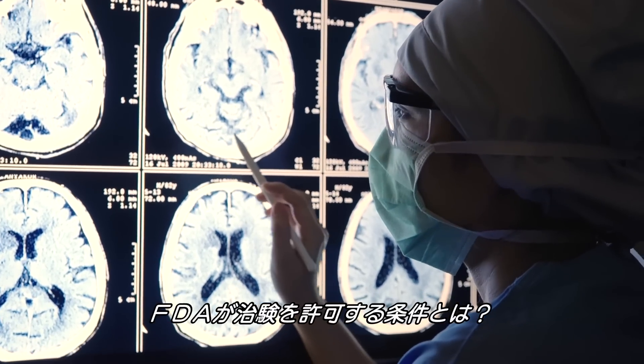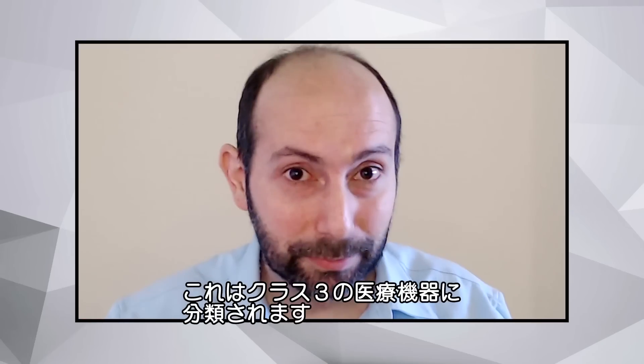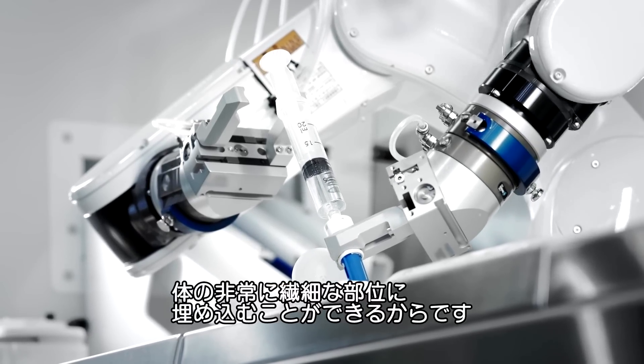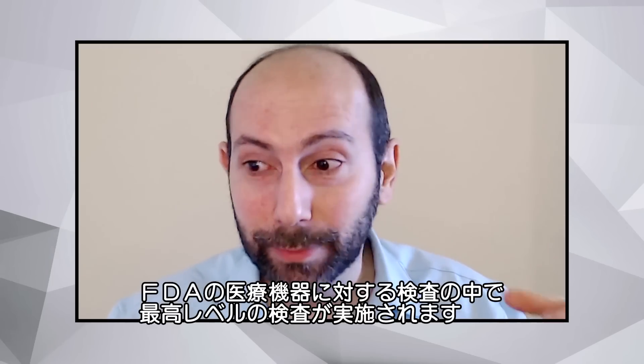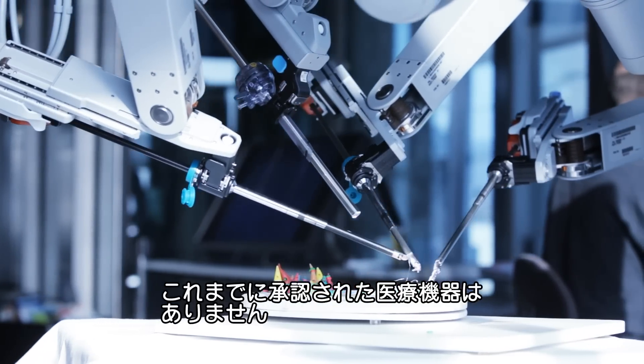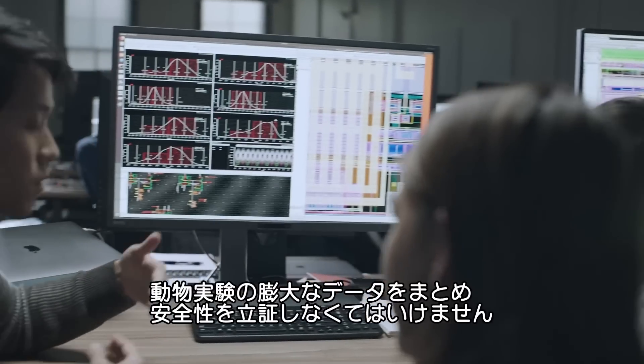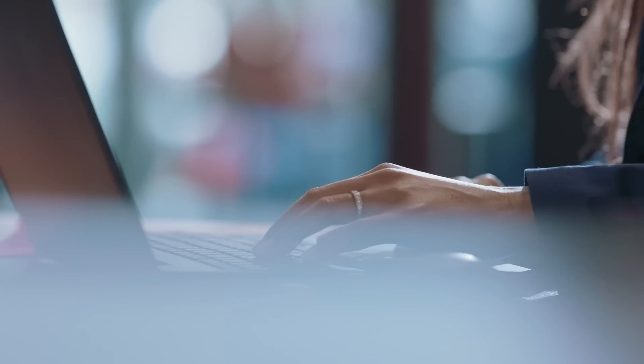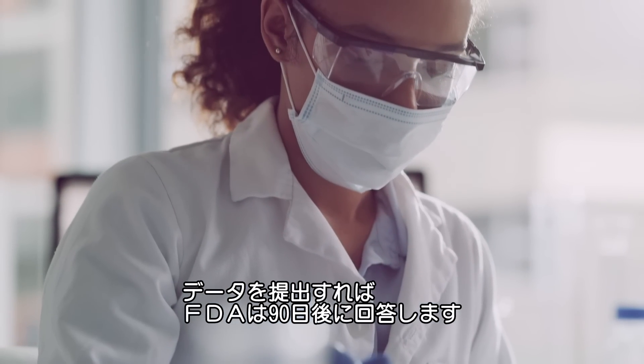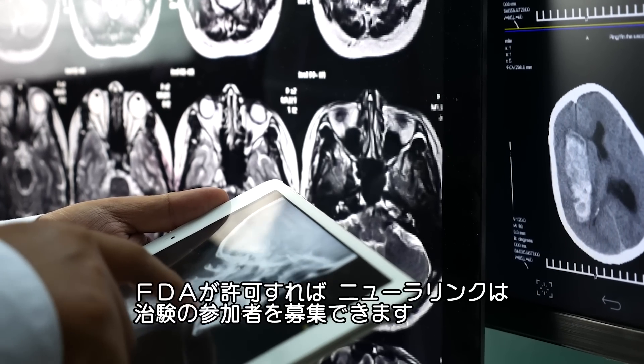So what would it take for the FDA to approve clinical trials in humans? The Neuralink devices are called class three medical devices. They are implantable and they're going into very sensitive body cavities. That is the highest level of scrutiny that the FDA assigns to medical devices. They don't have a predecessor — there's no previous approved example. So very appropriately, they have a high bar to cross. What Neuralink has to do next is prepare a very long and technical document with all the evidence from animal studies that their device is safe and effective. This document is submitted to the FDA, who has 90 days to review and give them an answer. If the FDA says yes, then their clinical trial is approved and Neuralink can enroll and recruit human participants.